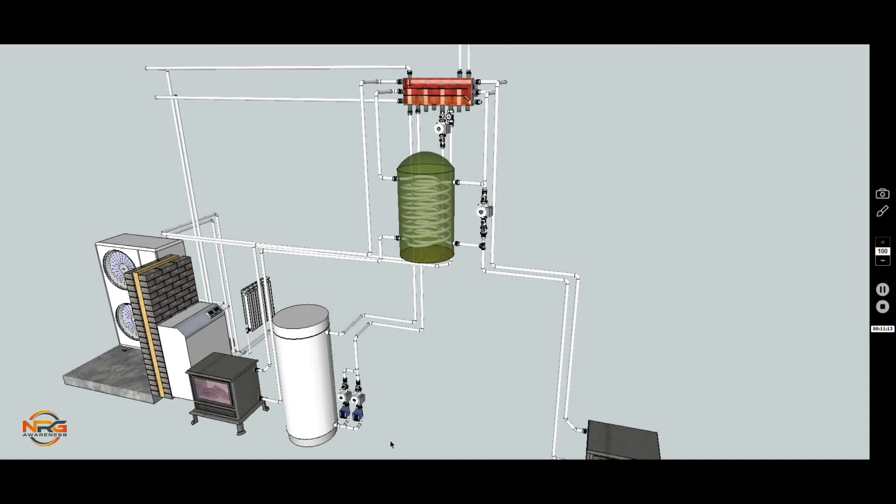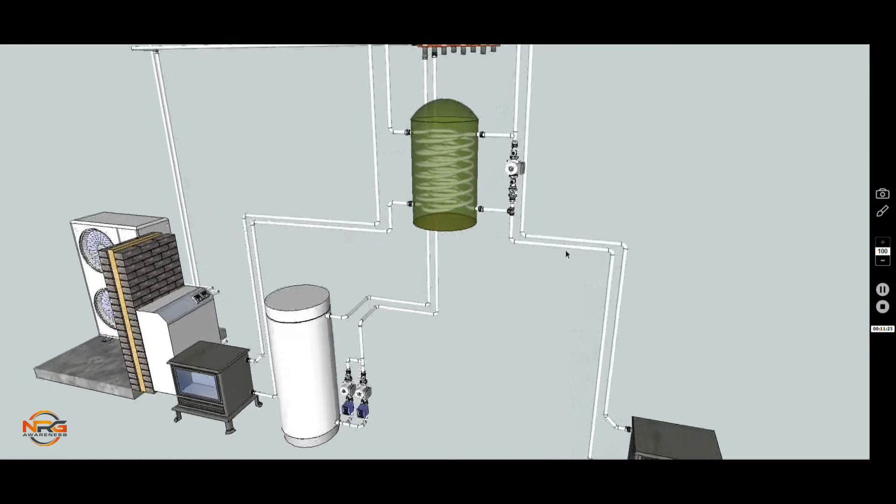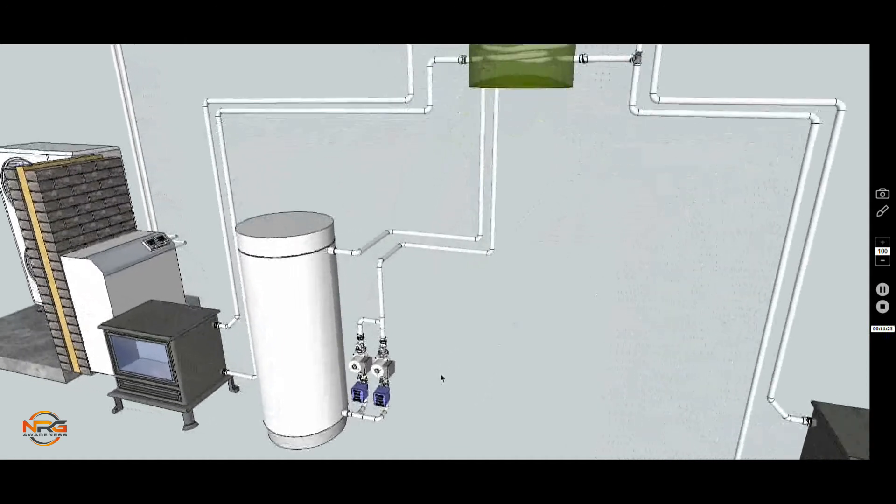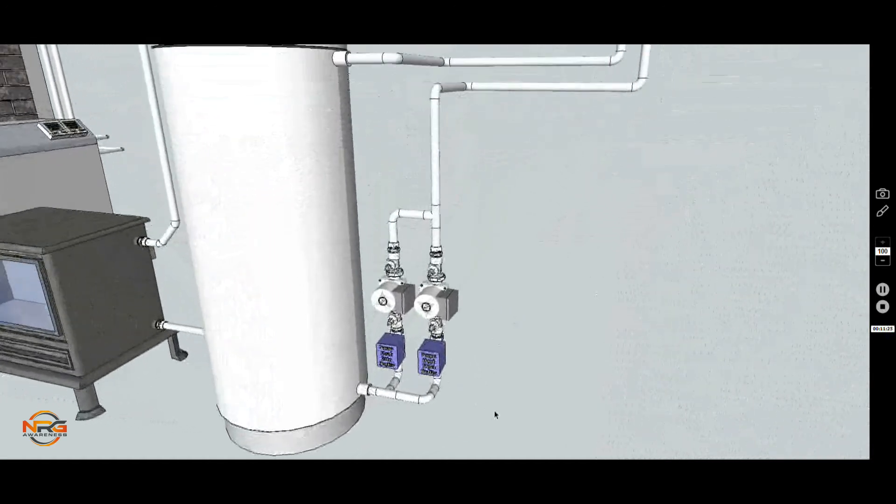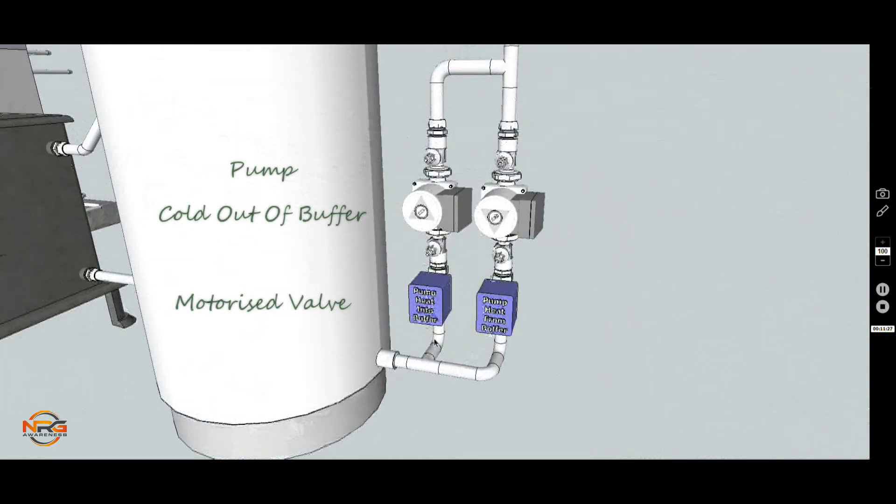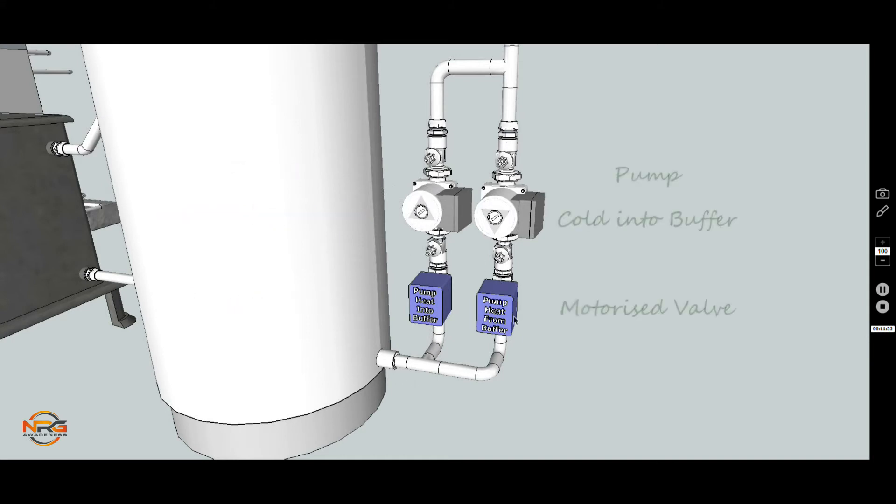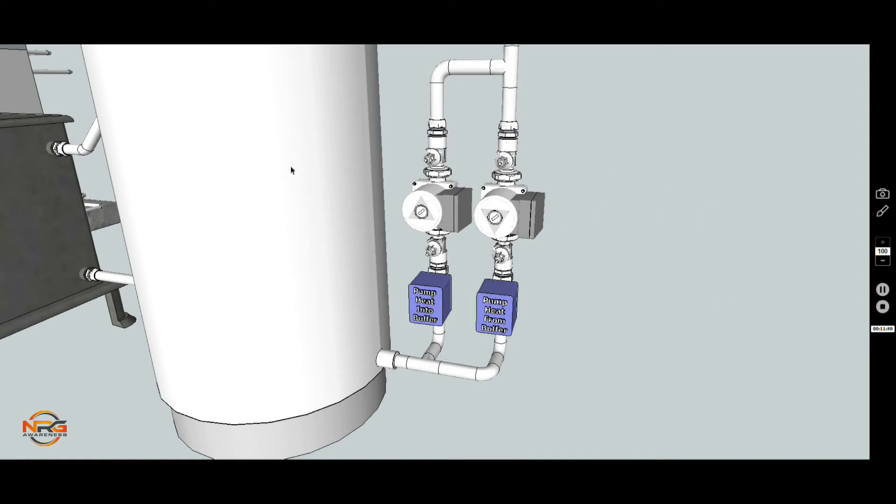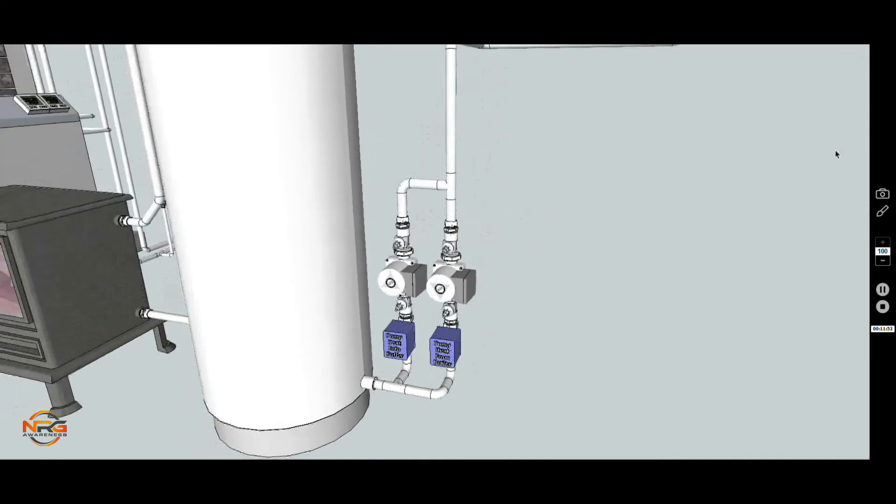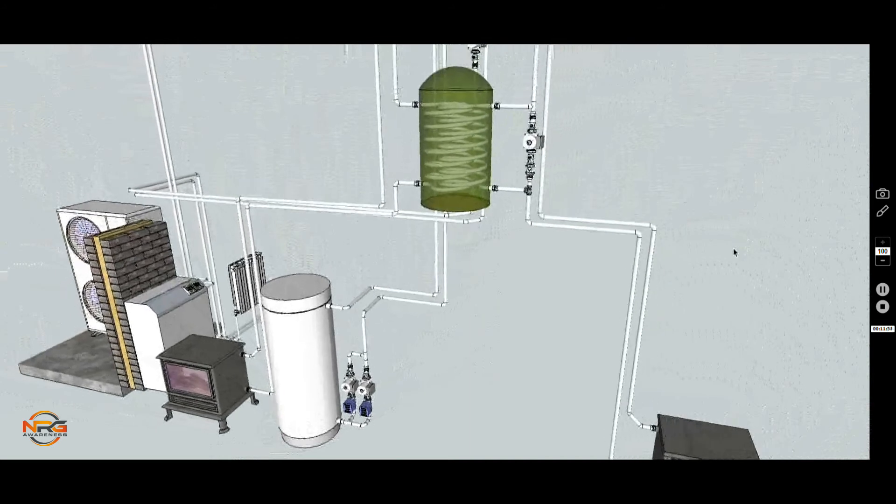If you look at the zone pumps, you're going to see that this valve would have to open for this pump to pull the cold water out. If I'm pulling cold in, I'm pushing hot out of the buffer, and if I'm pulling cold out of the buffer, I'm pulling hot water in. So the choice is mine. Do I want to heat the buffer and store the heat, or do I want to use the heat within the buffer?